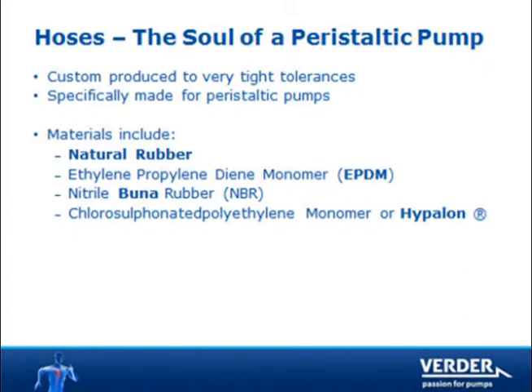Peristaltic pump hoses are made to very tight specifications for maximum working life. Hoses are available in several materials, including natural rubber for general applications, EPDM for corrosive products, Buna for oil and solvents, and Hypalon for high strength acid.